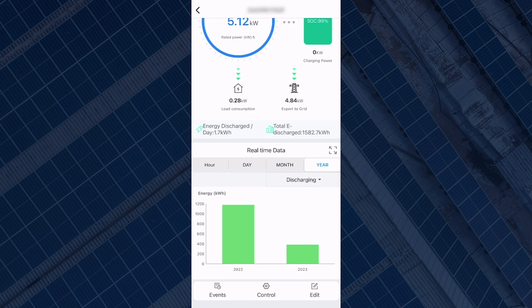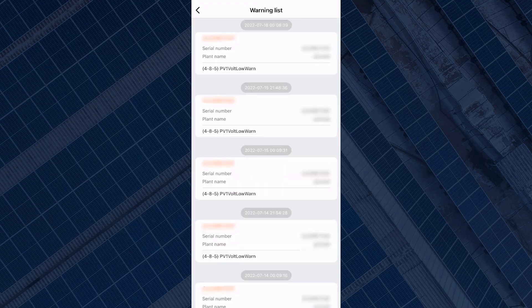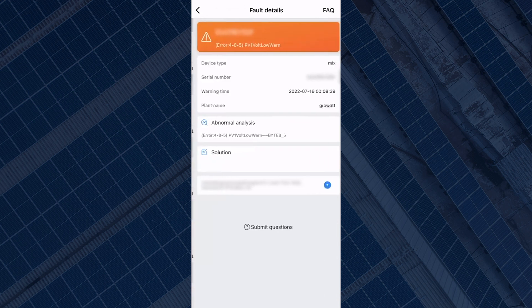At the bottom of the screen you have events, control, and edit. Events will usually log any issue with the inverter. In this case the last fault or warning was on the 16th of July 2022 — a PV1 low voltage warning — which has since been resolved. Whatever issue occurs with the inverter it will be logged in the events list, and if you select the error it may tell you a solution and give you more information about that error.